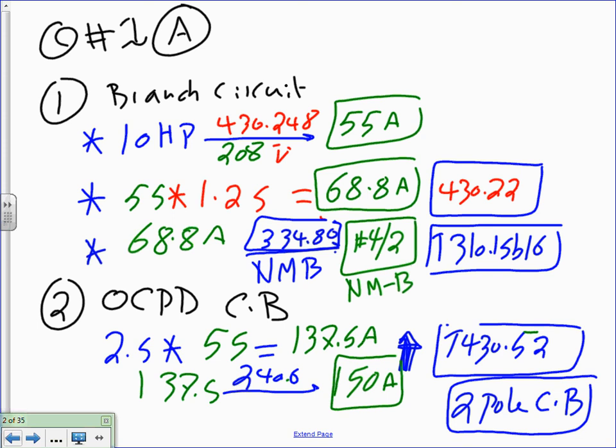Any question, guys? Brian, my friend. Go ahead, Brian. What was the 137 point? 137.5 is the full load current times 2.5. Yes, this is the 55 multiplied by 2.5.